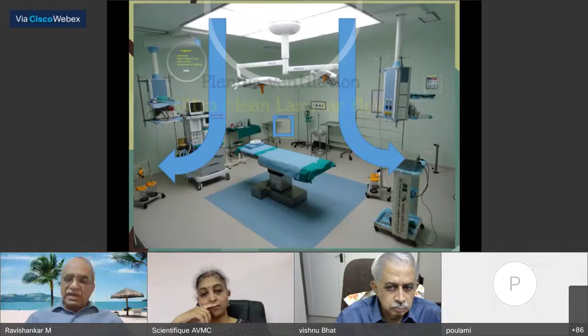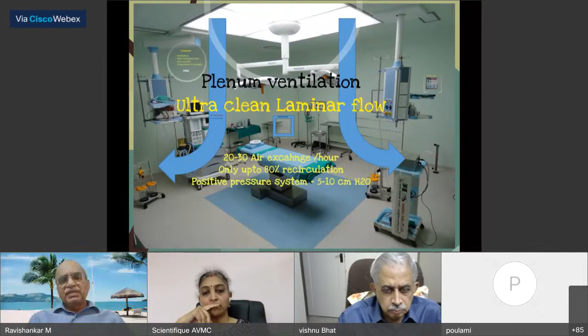If you look at it, this is a picture of the theater, and the airflow pattern inside the theater has to be a laminar flow. Plenum ventilation, ultra clean laminar flow is what is expected by the certification agencies. Ultra clean laminar flow, what is it? The airflow has to be 20 to 30 air changes per hour. Only up to 80% of the air should be recirculated and the rest should be fresh air taken in. And inside the theater, a positive pressure system should be maintained, 5 to 10 centimeters of water.